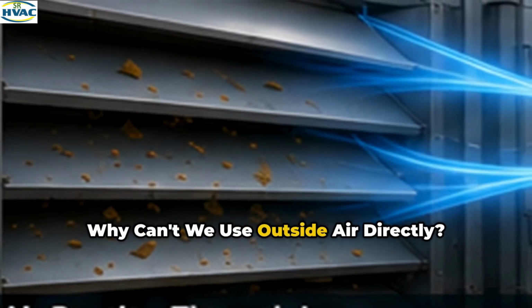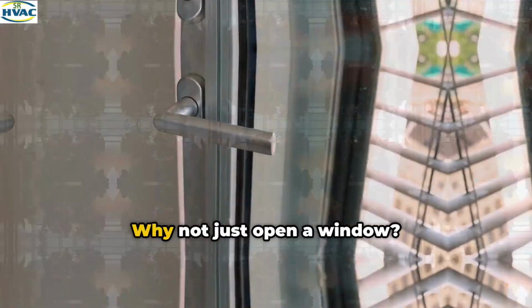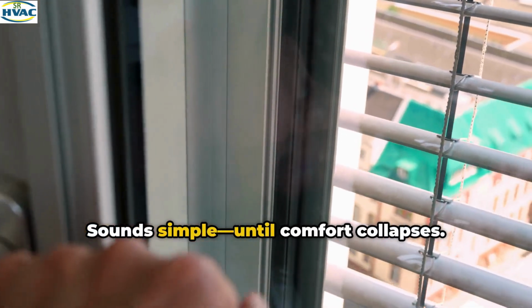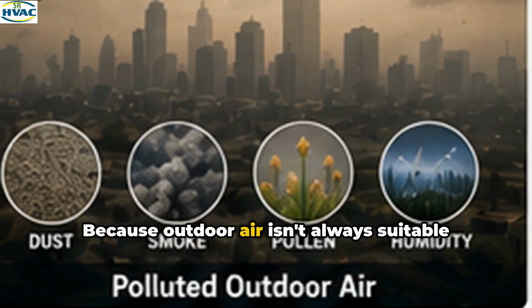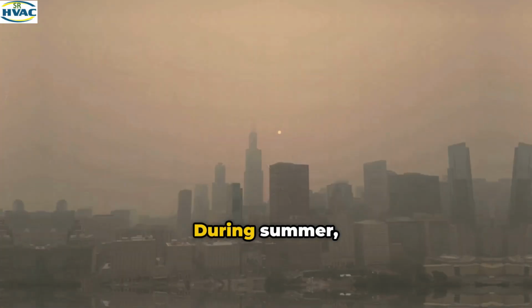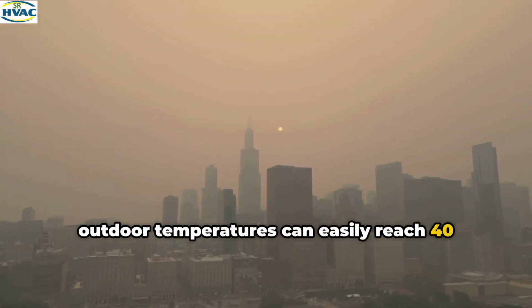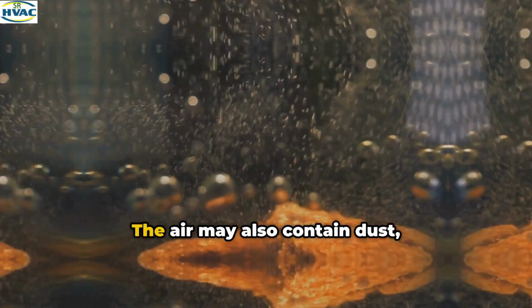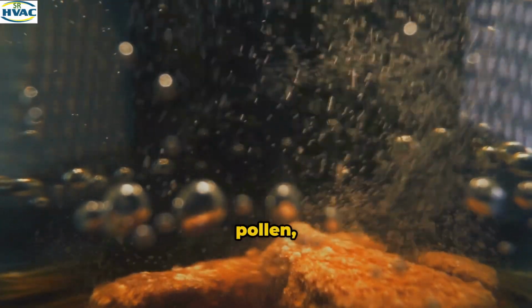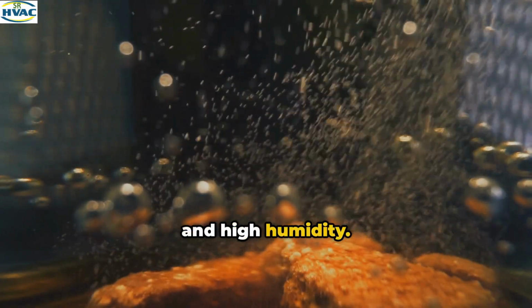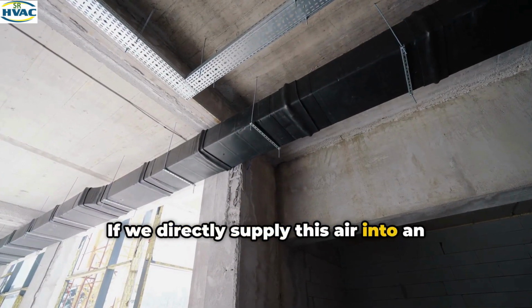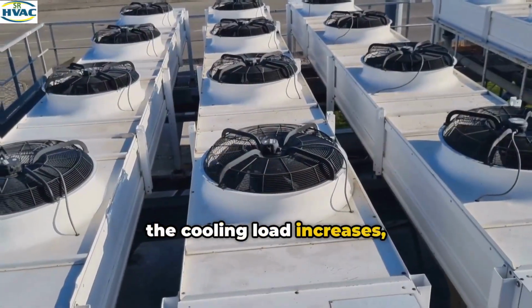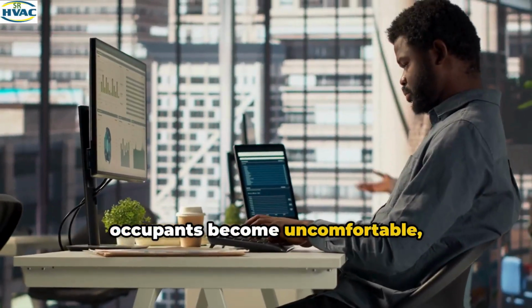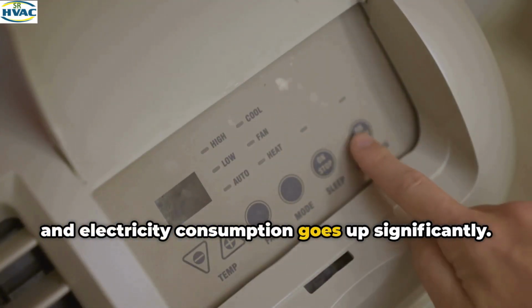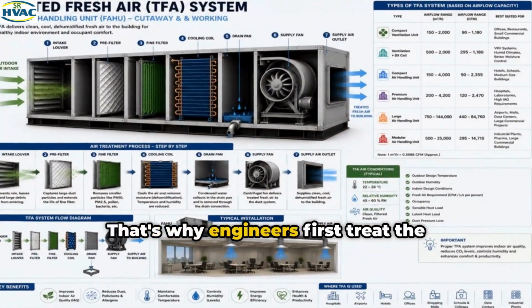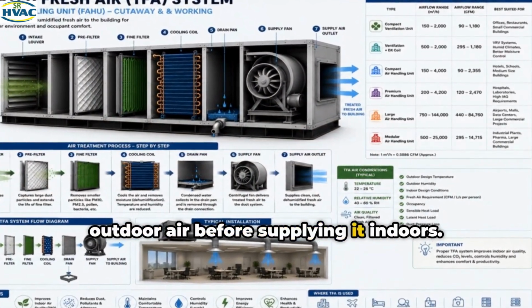Why can't we use outside air directly? Now you might think, why not just open a window? Sounds simple until comfort collapses. Because outdoor air isn't always suitable for indoor comfort. During summer, outdoor temperatures can easily reach 40 to 45 degrees Celsius. The air may also contain dust, smoke, pollen, bacteria, unpleasant odors and high humidity. If we directly supply this air into an air-conditioned building, the cooling load increases, humidity rises, occupants become uncomfortable and electricity consumption goes up significantly. That's why engineers first treat the outdoor air before supplying it indoors.